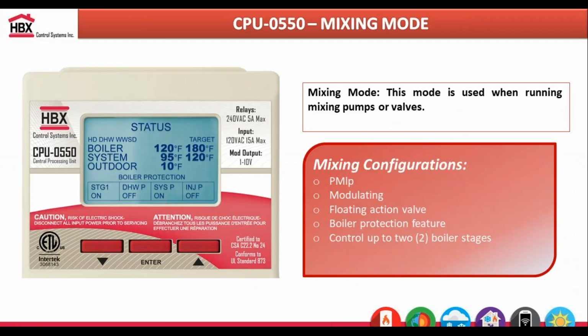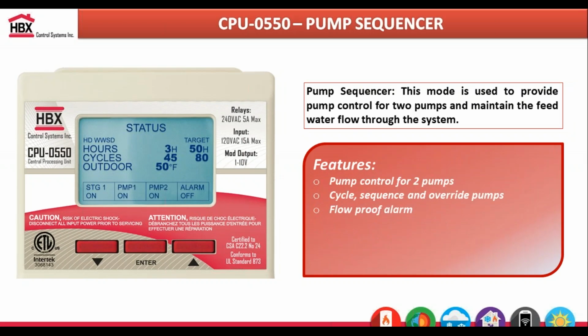So again, for staging, we can do 3 on and off boilers or a single modulating boiler. In terms of mixing mode, we can control an injection pump or a 3-way mixing valve, a modulating pump or valve. So you have those 3 different options on the controller to control a mixing device.